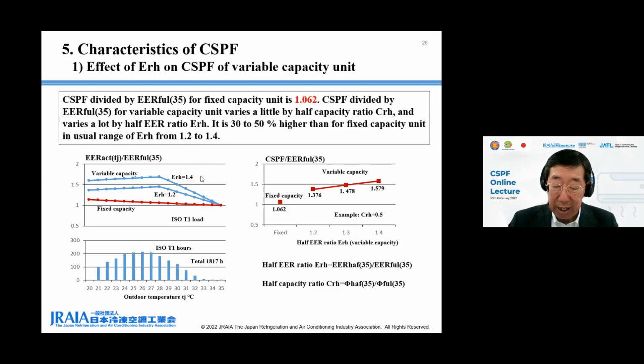The lower left figure shows ISO T1 bin hours at each TJ. The right figure shows Cspf divided by 35 degrees C full EER for fixed capacity unit and variable capacity unit with different half EER ratio Erh from 1.2 to 1.4, which is usual range in laboratory tests. Cspf divided by 35 degrees C full EER is a kind of weighted average of actual EER divided by 35 degrees C full EER. It is 1.062 for fixed capacity unit.